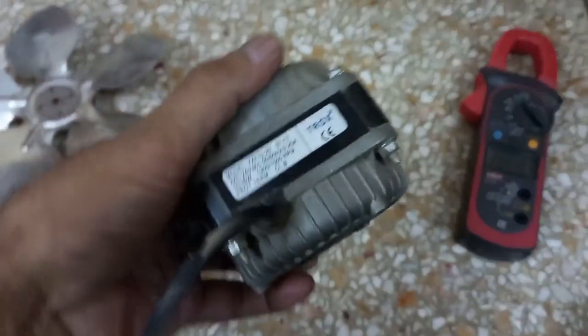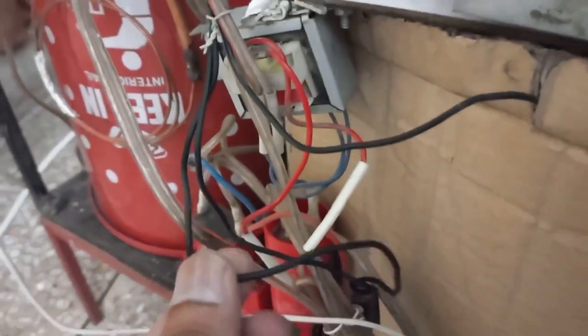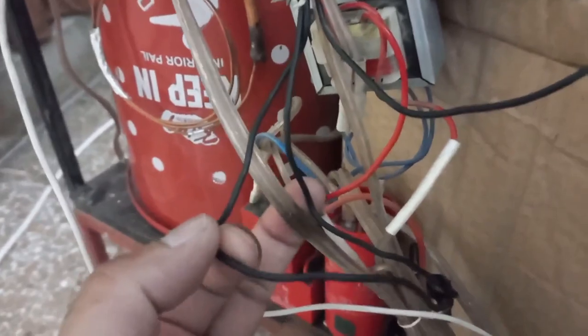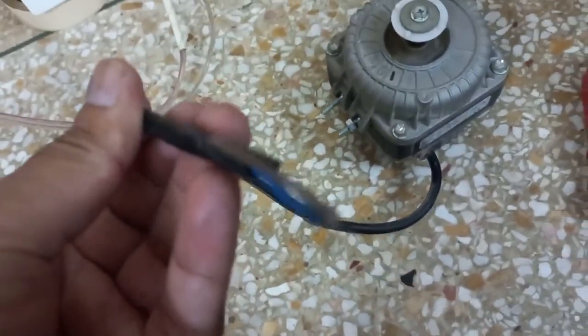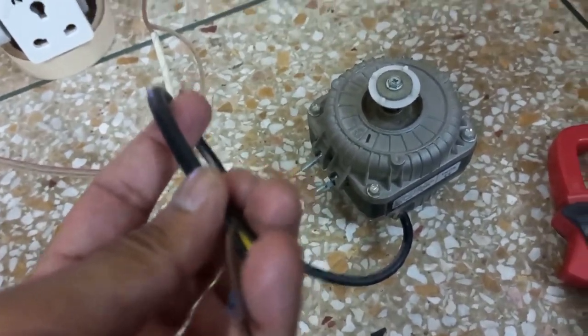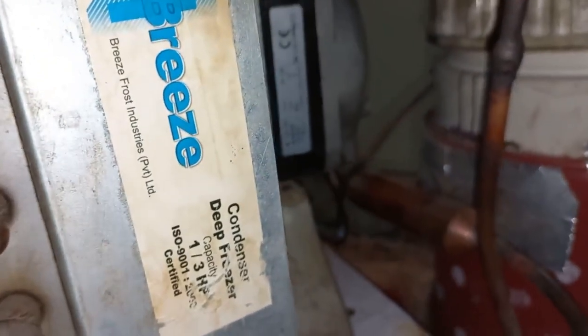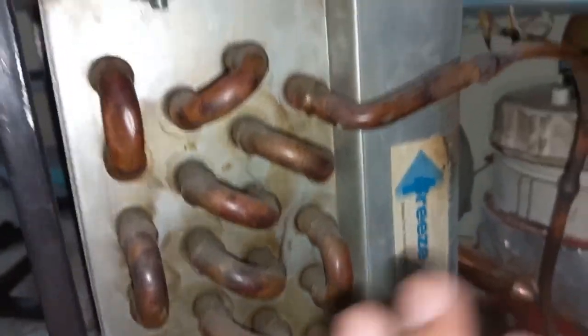This was the old one, 36 watt 0.25, and this new fan has little bit better wires, two separate wires, good quality, and this one has one wire but a little bit thin, its quality is not too good. Now the summary is, it's better to bring the condenser with a fan fitting from the company, that will be a 100% match. When I bought this 1/3 HP condenser, the shop person gave me this 0.35 fan, and he said this is a big condenser, so you need this big fan. But as this was not fitted on this condenser, I tried to fit this, and it was also working.